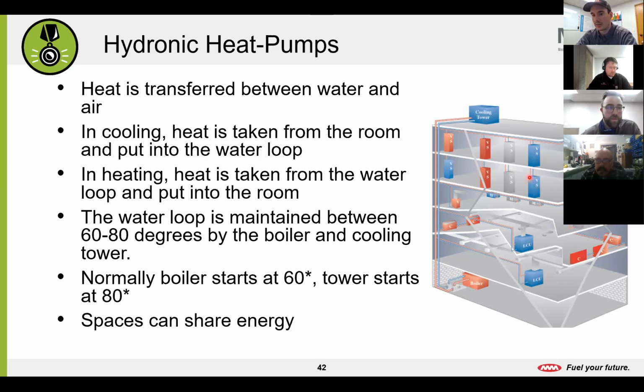And what's cool about that is, if there's a unit in the building that's in heating mode, we can take the heat we just absorbed and go over to a unit that's in heating. Because when a system is heating, it is pulling heat from the water and putting it into the air. So we're really just picking up heat from air here, dumping it into water, and then we're pulling heat out of the water and dumping it into the air in a different spot. You'll see on this a boiler in the basement and a cooling tower up top on the roof. So we'll specifically dig into those. But the basics of a hydronic heat pump system is that the heat is transferred between water and air like it says on here. In cooling, heat is taken from the room air and put in the water loop. In heating, heat is taken from the water loop and put into the room.